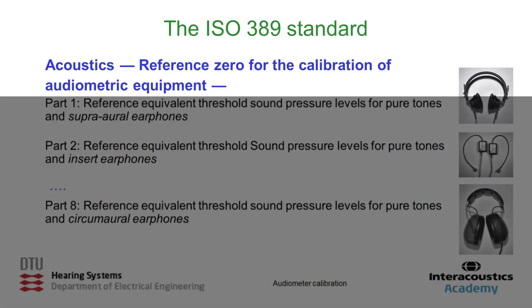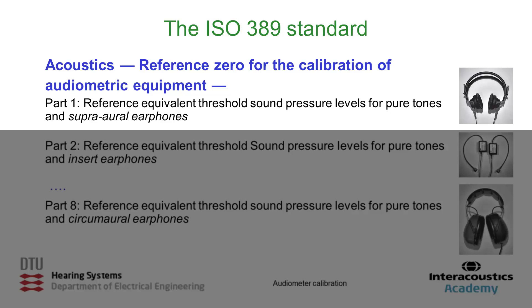This family of standards has the main title: 'Acoustics — Reference zero for the calibration of audiometric equipment.' Part one is titled 'Reference Equivalent Threshold Sound Pressure Levels for Pure Tones and Supraaural Earphones' — earphones sitting on top of the pinna. The meaning is simply to specify how much level you need to measure in your ear simulator in order to calibrate correctly.